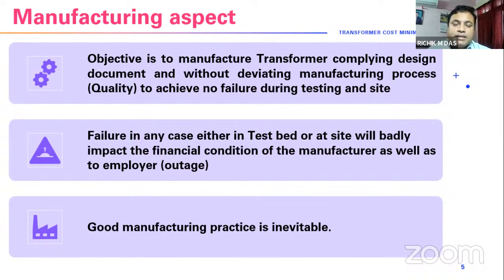Failure means test-bed failure or failure at site. Once there's a failure, either in the test bed or at site, you have to reopen the transformer, change whatever failed, and then remake it for testing. This process has to be repeated again and again, which delays your process and delays other transformers too.